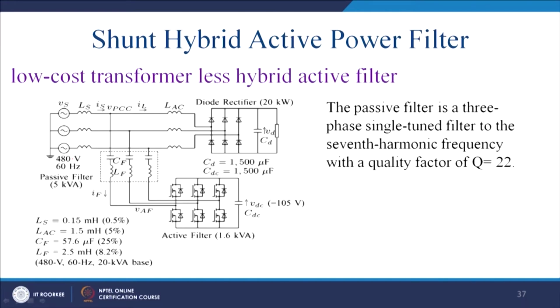and you can see that it is a 480 volt 60 hertz supply, and the dc voltage is maintained at 105 volt, and this is a filter, and this has been tuned to some desired frequency, fifth or 7, it has been tuned to the 7, and the passive filter power rating is 5 kVA, and the diode rectifier power rating is 20 kVA, and with these combinations, you only require the active power rating of the active power filter reduced to be 1.6 kVA, and we assume that source inductance will have around 0.15 millihenry, that is 0.5% of the base value.